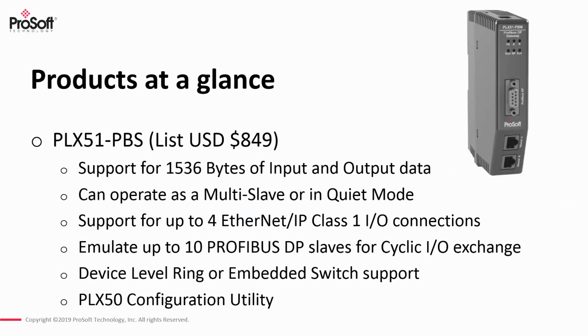Additionally, we've got a separate product, which is the PLX51 PBS. This module has a lower list price, also supports up to 1,536 bytes of input data. Essentially, this module has all the same functionality as the PBM module without being able to support PROFIBUS DP master. So as you're specifying a project, if you're not sure whether you need to be a PROFIBUS DP master or PROFIBUS DP slave, the PBM module is a good solution because it can operate in either mode.